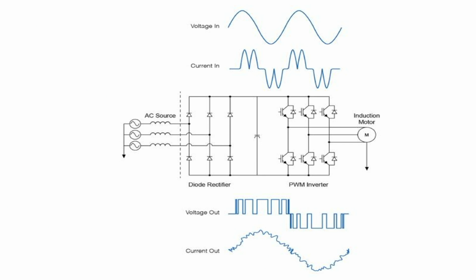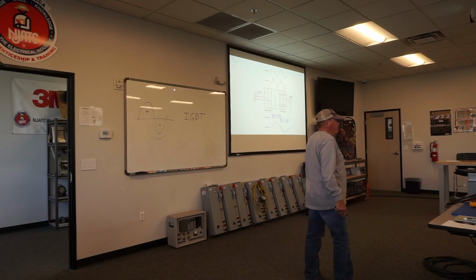So, our input voltage looks like this, and because of this high speed switching, IGBT, it affects the current. And so there's what the current on the input side of the drive looks like. And so this affects the grid out here. This current that's now feeding back out on the grid will affect the grid voltage, causing voltage distortion. Because as that current drops, that's one cycle right there. That's one half cycle on the positive side. There's the other half on the negative side. So that's one cycle from there to there. So that's happening twice per cycle, so that's 120 times a second. So that generates a lot of dirty power. Drives are the biggest culprit of dirty power.